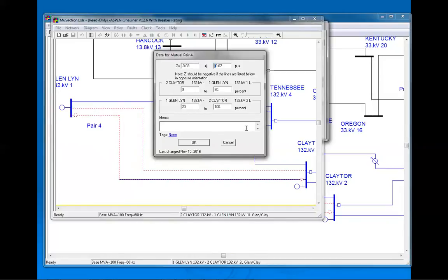Okay, and again, this happened because when someone enters line 1, they select one orientation, and when someone adds line 2 to the same circuit, to the same network, they happen to select the opposite orientation. So this got recorded in the network model, and it's showing up like here, and it can confuse a lot if you enter mutual coupling with percent and so on.